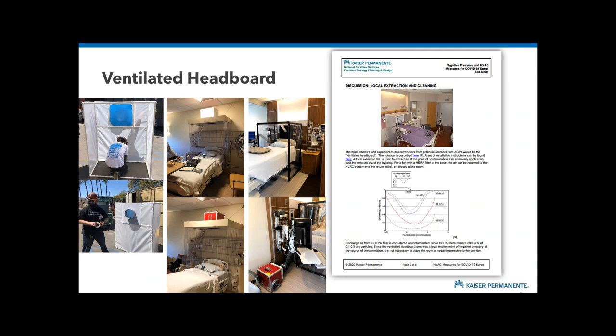Okay, great. Is there a cap on acceptable relative humidity for rooms with COVID patients? No, generally, well, I don't know, within Kaiser, generally we follow the 60% high-end range or 65% high-end range. I've always argued that 60 and 65% are a little moot because of the way that humidity sensors and humidity control systems work. But I think most of our spaces are controlled to that 60% limit, including office buildings and clinics and spaces like that. So if you have a building that's not controlled to a high end of 65, I would probably be concerned about that, but not because of COVID, because of mold and some other standard IAQ issues.